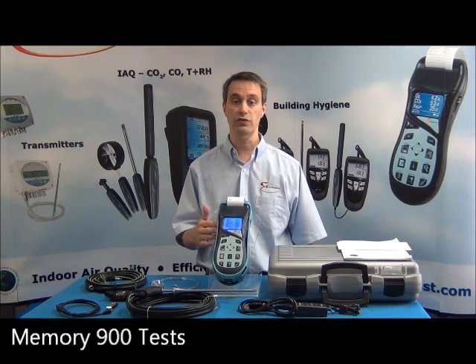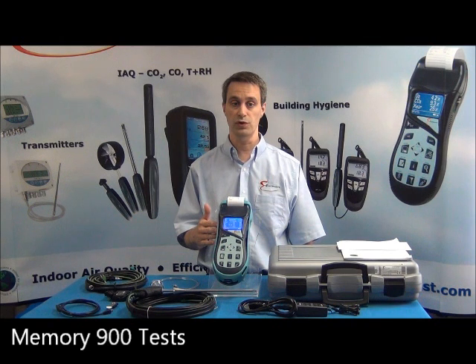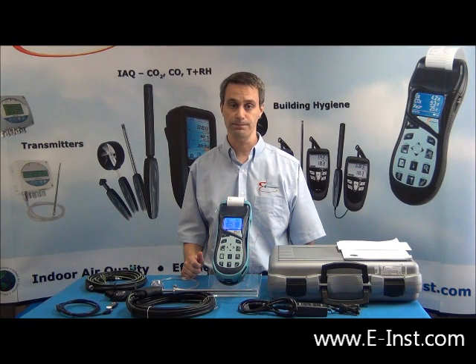The internal memory can store up to 900 tests with user-programmable tag names for different sets of data. The software can be used to transfer saved data from the analyzer's internal memory to the user's computer. Data transferred to a computer can be viewed in an Excel spreadsheet and exported out.